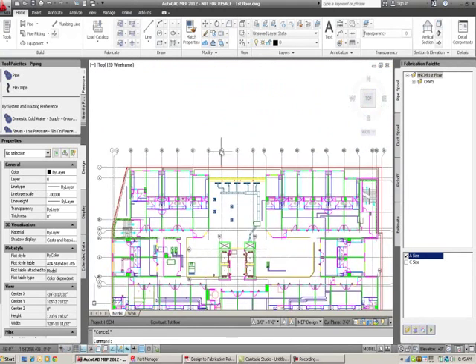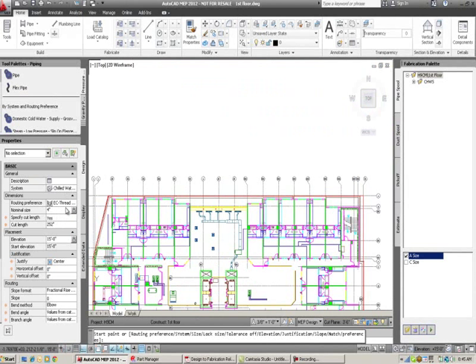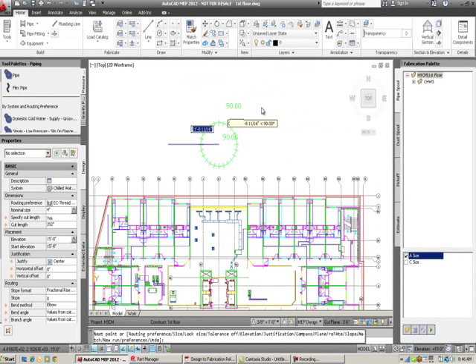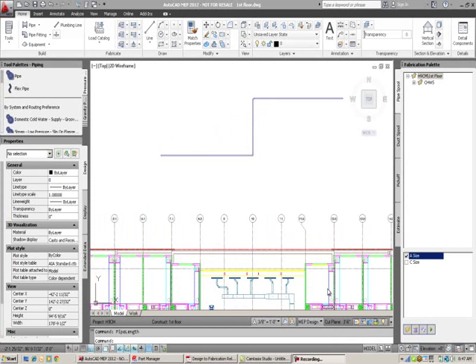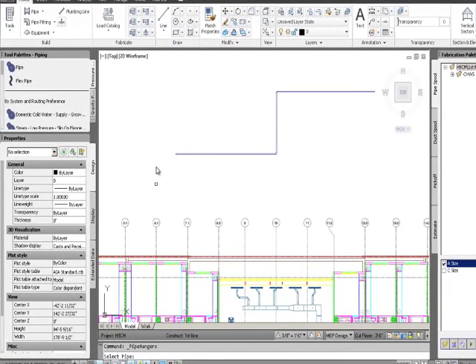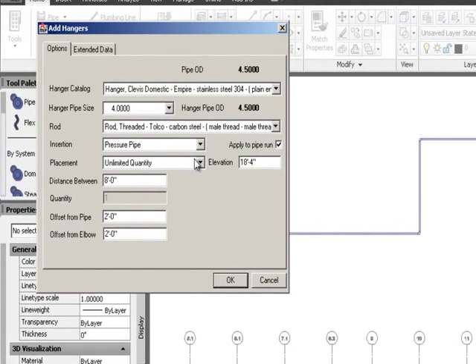Another feature is hangers. I'll place some four-inch pipe at 15-foot elevation by running it out a couple of times. Then I go to select hangers and follow the command prompt at the bottom of the screen — select the pipe to put hangers on. A dialog box comes up automatically picking the correct four-inch hanger for my pipe.